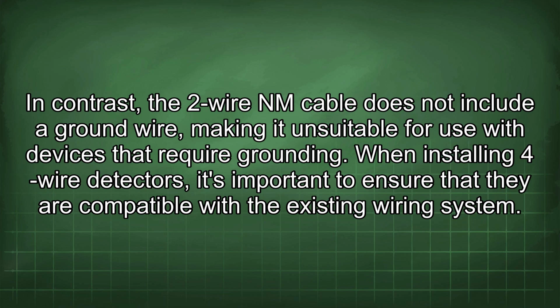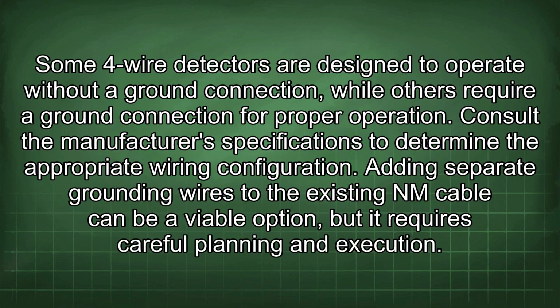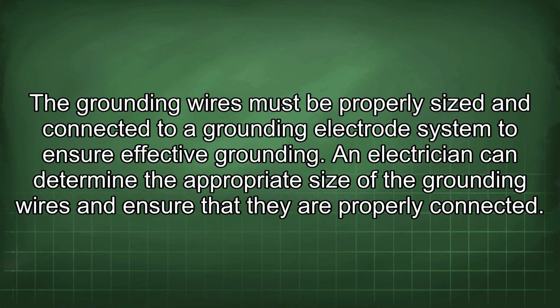When installing 4-wire detectors, it's important to ensure that they are compatible with the existing wiring system. Some 4-wire detectors are designed to operate without a ground connection, while others require a ground connection for proper operation. Consult the manufacturer's specifications to determine the appropriate wiring configuration. Adding separate grounding wires to the existing NM cable can be a viable option, but it requires careful planning and execution. The grounding wires must be properly sized and connected to a grounding electrode system to ensure effective grounding. An electrician can determine the appropriate size of the grounding wires and ensure that they are properly connected.